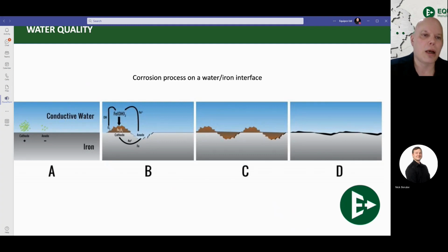But let's just first talk about the conductivity of water inside of a system. Anytime that you add heat to water, it becomes electrically conductive. That's just physics. Again, you can argue with physics all you want, but it's going to win. So when we have electrical conductivity in our water, we're going to have buildups of these magnesiums and calciums, and that'll start to pit and eat away at these systems or create little mounds of calciums, limes, and stuff like that, which will lead to pitting on the inside of a heat exchanger. Pitting is then eventually going to lead to leaking on the inside of your heat exchanger, or pitting and pinholing in pipes.